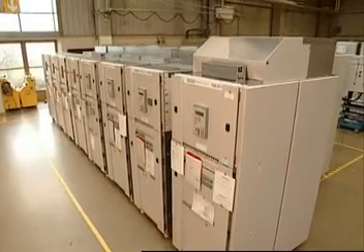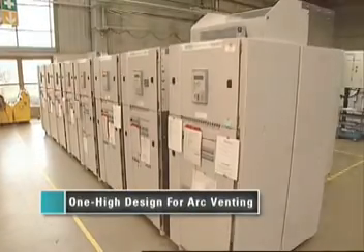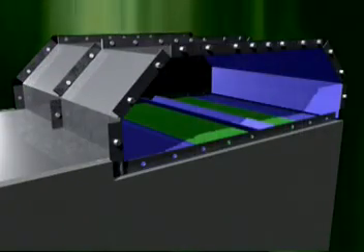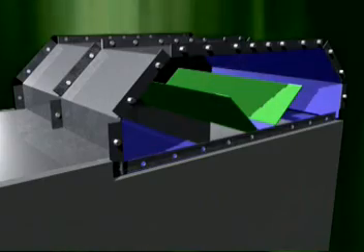To offer the safety of arc venting, we developed the NX Air P with a one-high breaker design. Many switchgear operators aren't used to this one-high design, so we've had to address a lot of questions about the NX Air P. As it turns out, only 15 to 20 percent of switchgear units in the United States have the breaker in the top compartment. We feel the arc venting benefits of the one-high design far outweigh any loss of stacking ability.